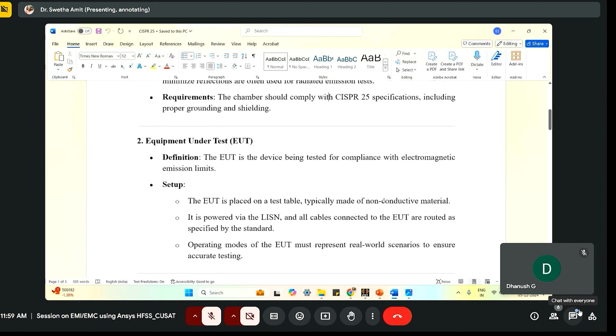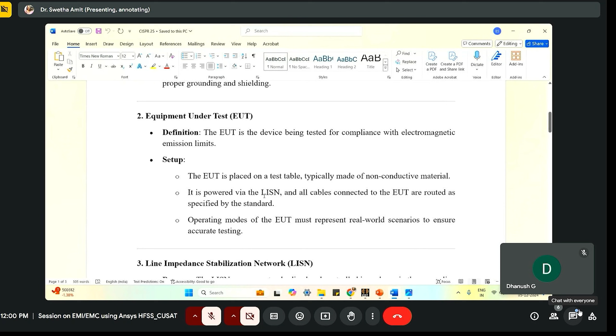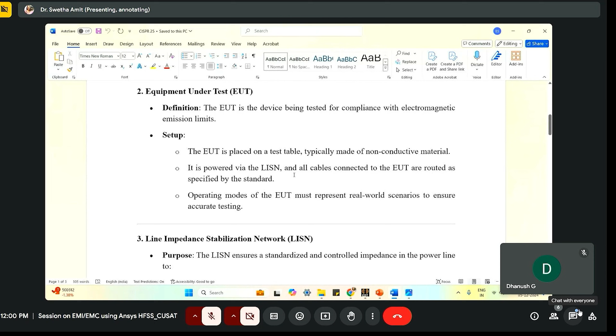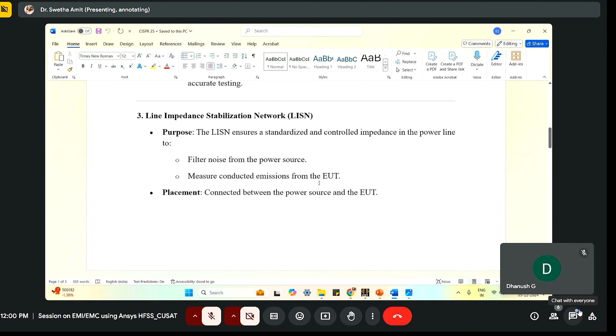What happens is I have my EUT kept on a non-conductive material. I can use, and I've used, wood here. It's powered via LISN, my line impedance stabilization network, and all the cables are connected as per my standard design. Coming to LISN, why is it important to feed the device under test via LISN itself? Because of the filter noise which it takes care of, and it measures the conducted emission from the EUT. So in this experiment, conducted emission can also be checked, or I can check the radiated emission.